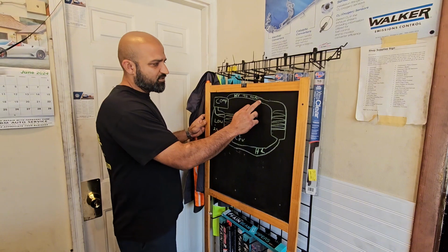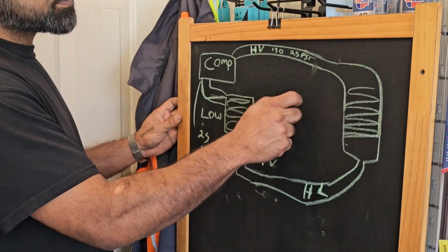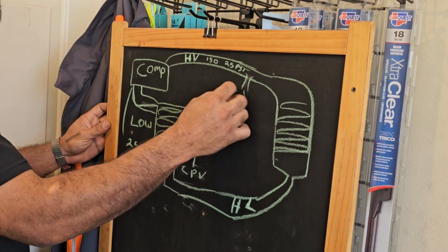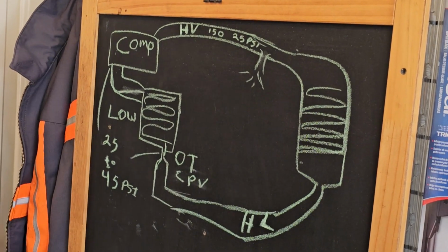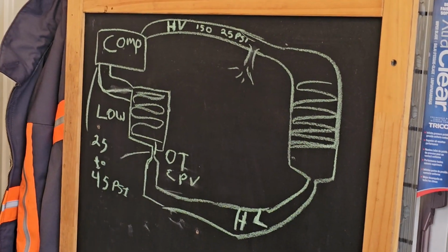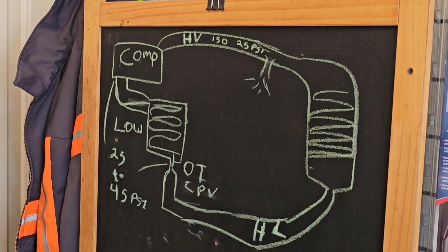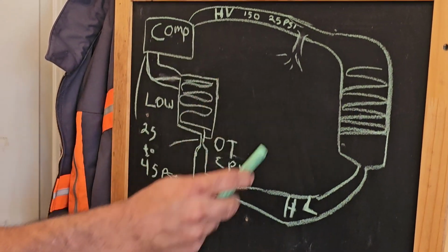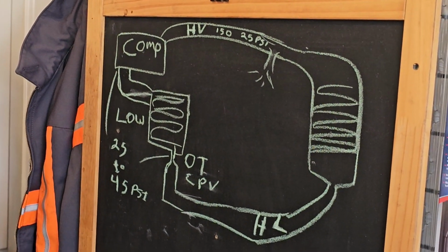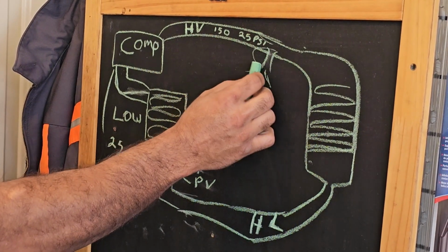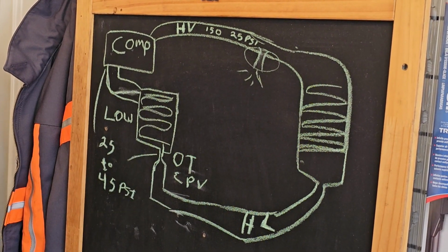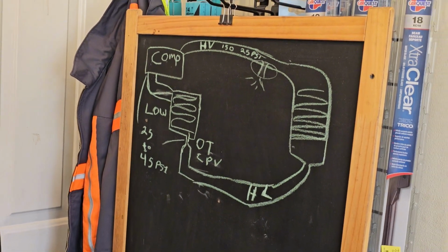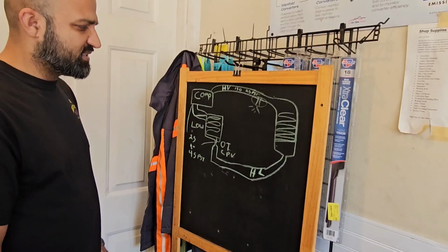If you have a leak somewhere in the system, as soon as the refrigerant comes out, it's going to boil out. So you're not going to be able to see where it's leaking from because it's not in liquid form anymore. It's just going to leak out as vapors. So we also put dye in the oil so it accumulates and we can find the leak under fluorescent light. That's a common way of finding a leak in the system.